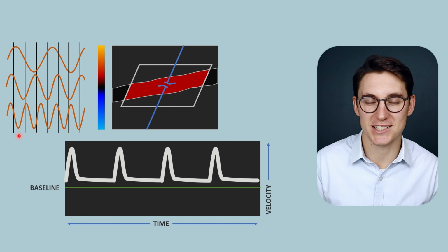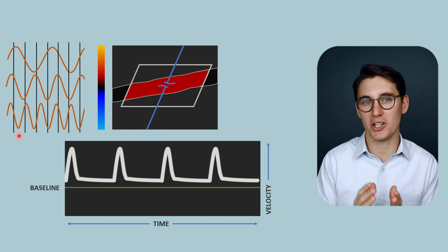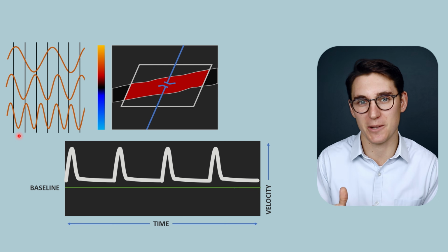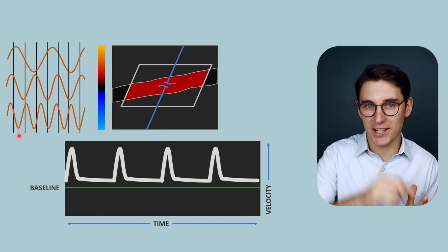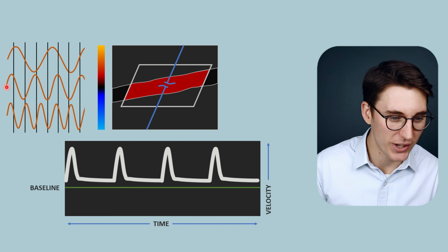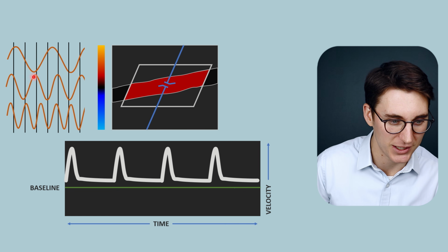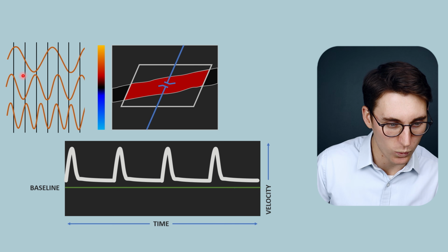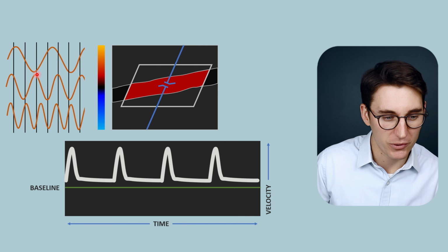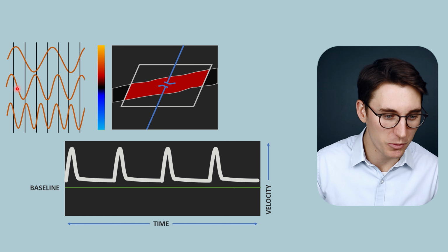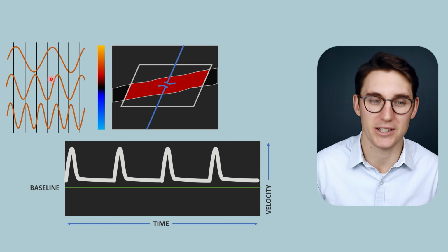Now, the Nyquist limit states that we need to sample a returning wave, a returning Doppler shift frequency, at least twice within one wavelength. So if we have a look at this wavelength returning, and we take two consecutive points on that wavelength, we take the peak here and the peak here, we can see that we've sampled once, sampled twice before the next wavelength starts. We will be able to accurately assess the frequency here.